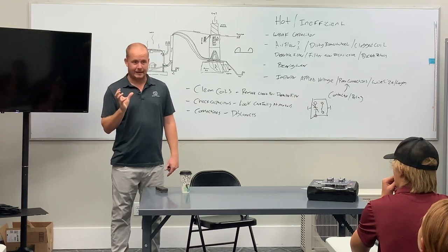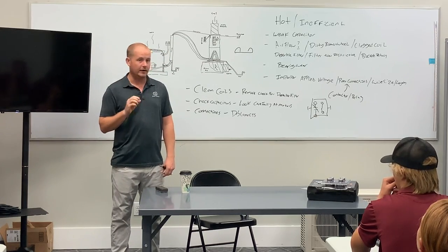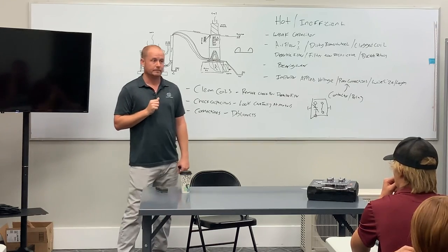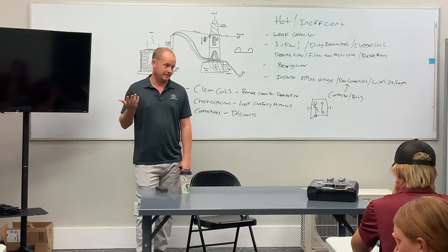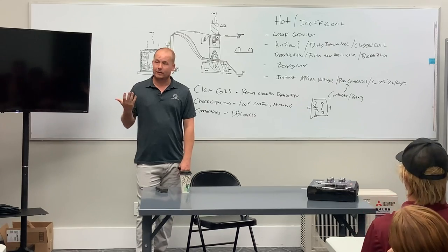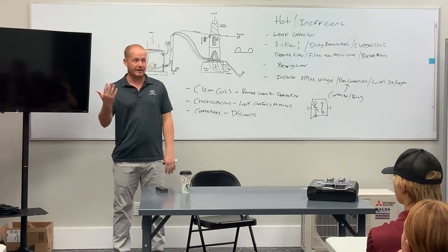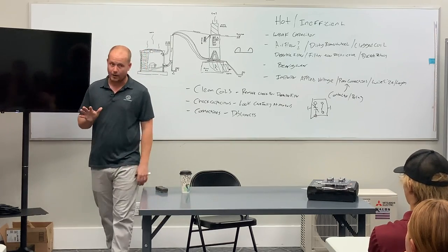When you open up that secondary little cover in there and you look at those terminals, if you see any signs of melting, arcing, whatever, that disconnect needs to be replaced. In addition to that, look and see if there's significantly smaller wires coming into it than going out of it. That's not necessarily a problem.